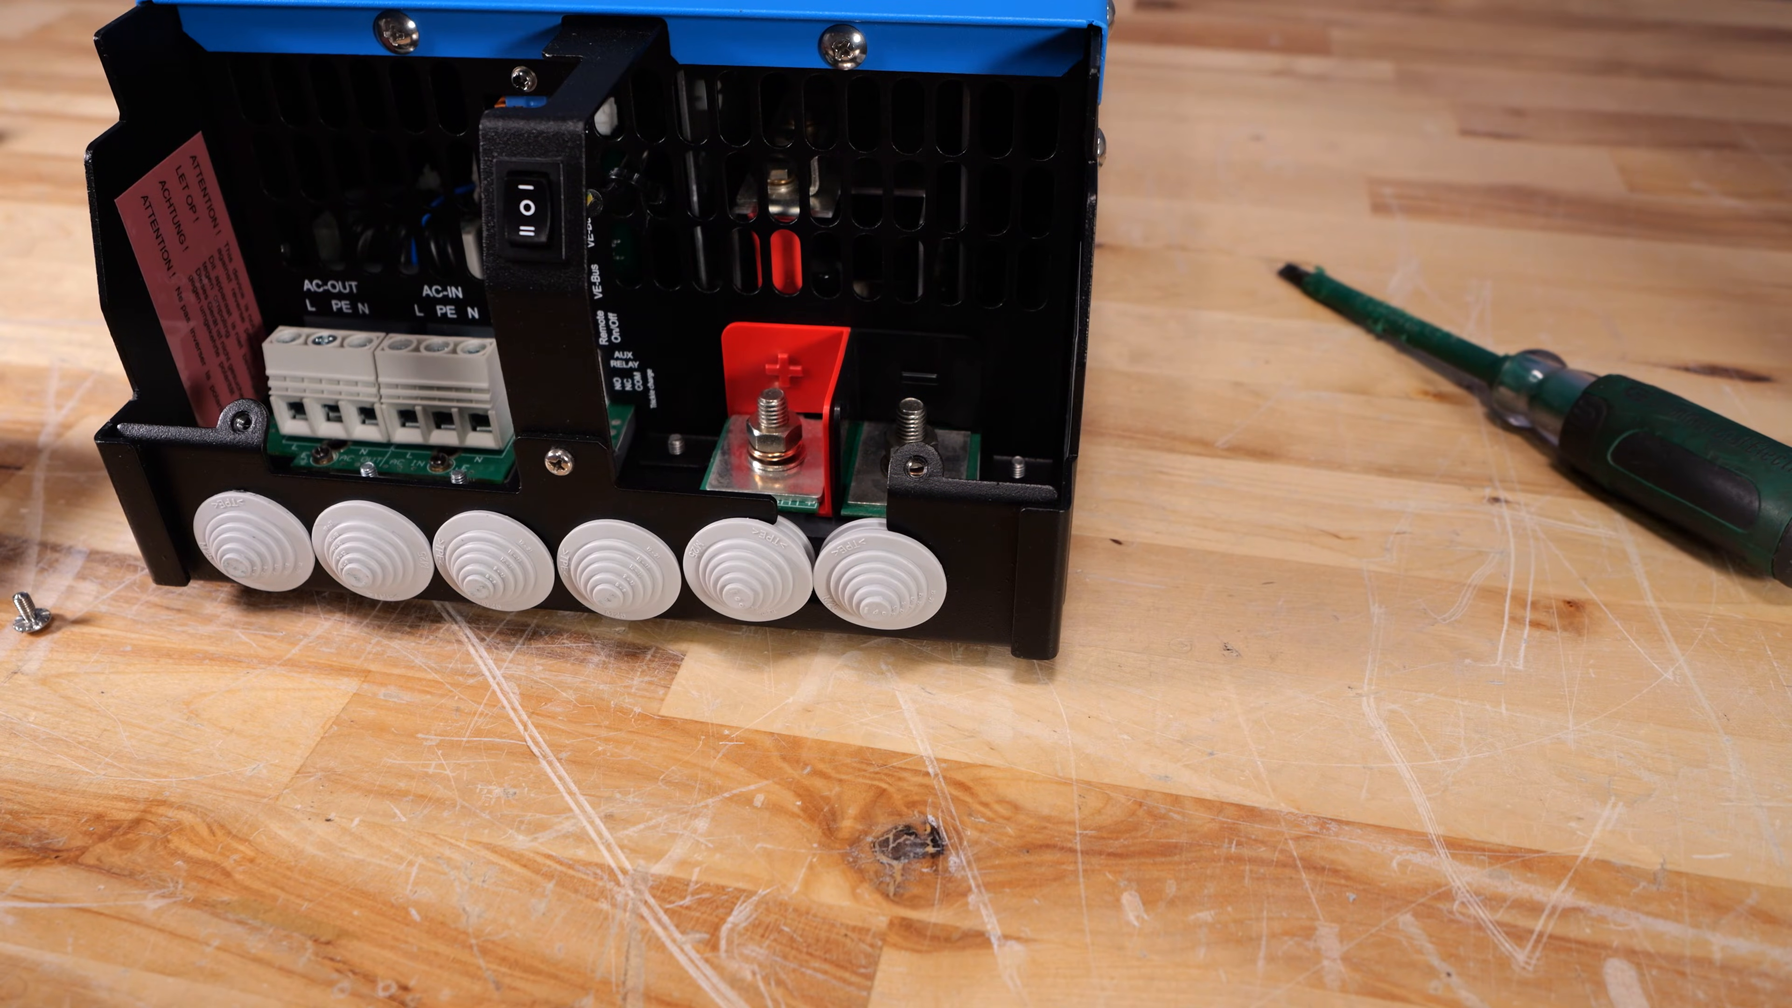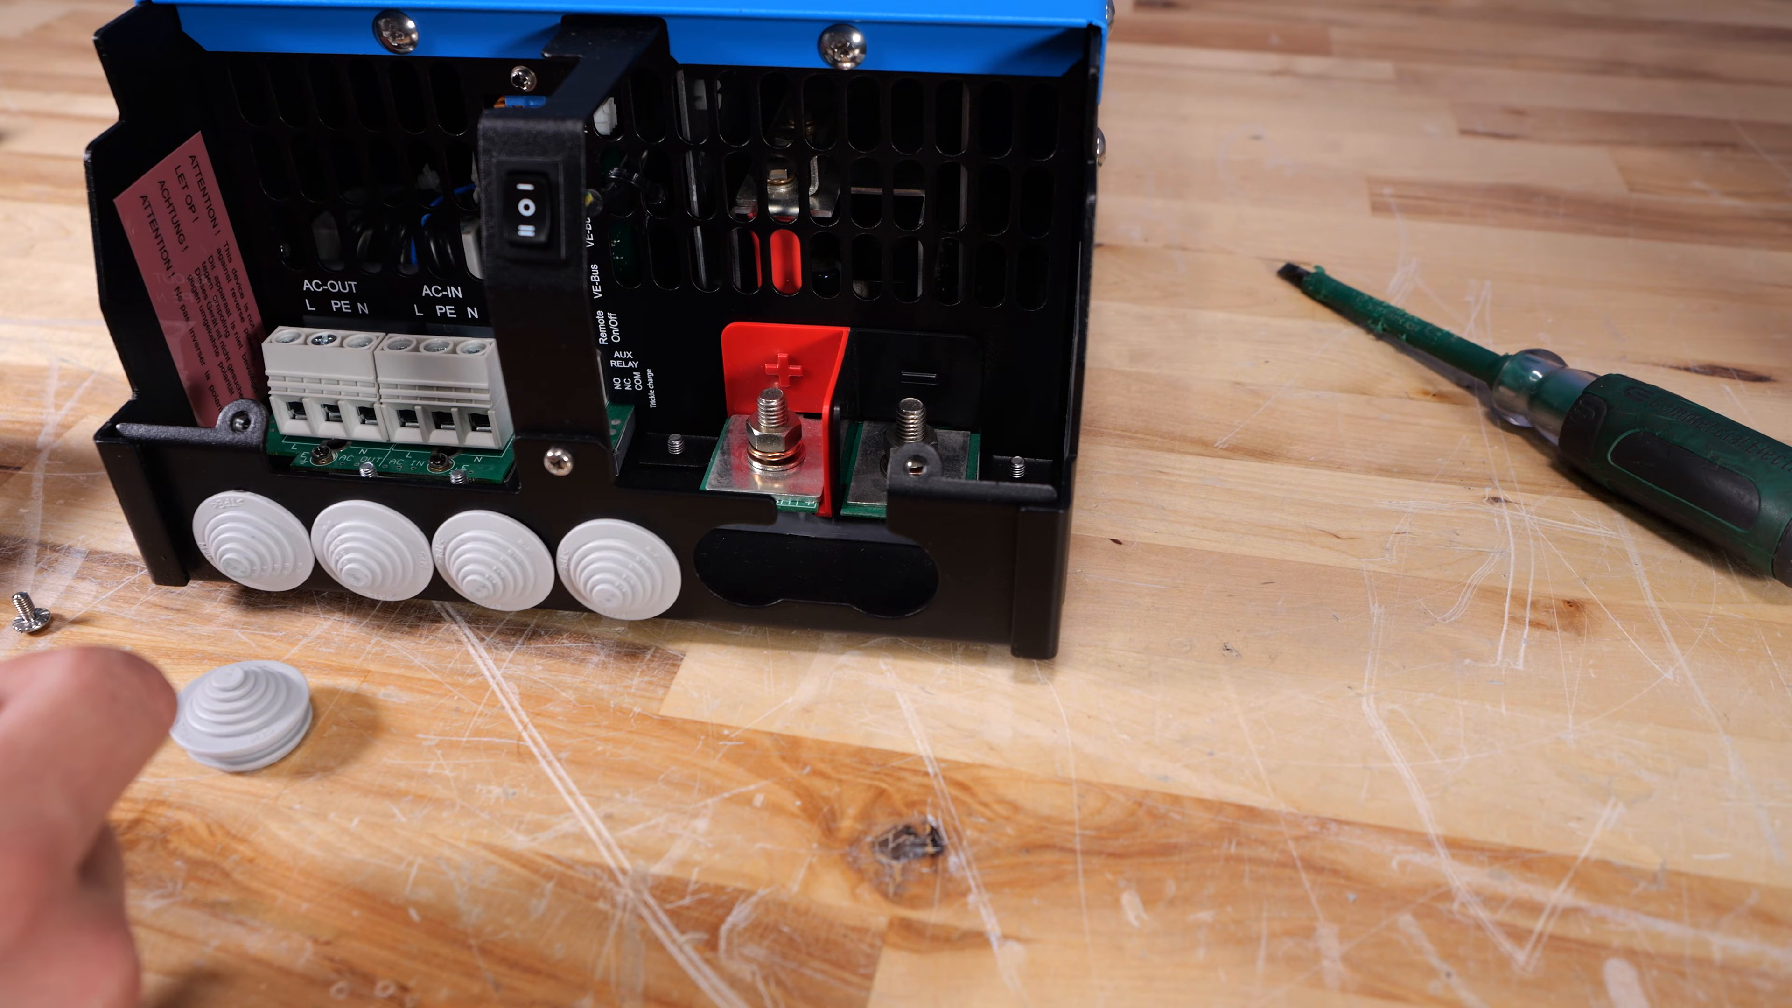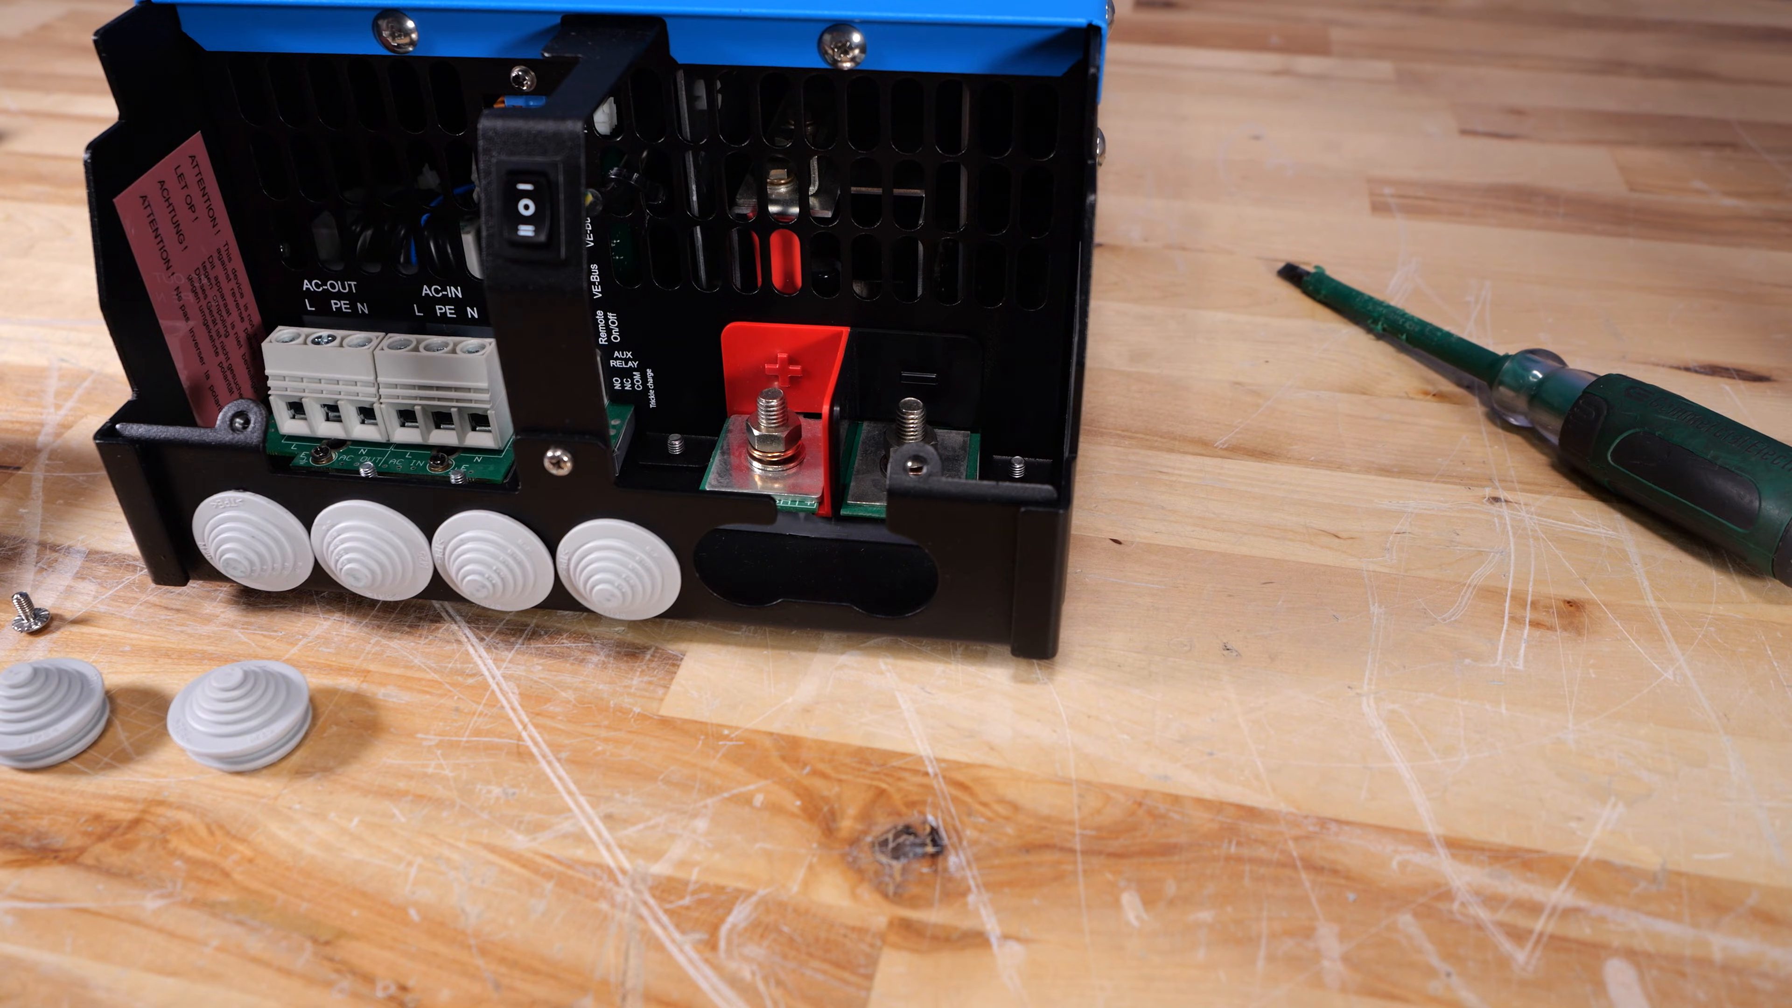As far as getting your cabling in and out of the inverter, they have these dust-proof glands I mentioned, and they made a nice notch in here, so if we remove the terminals for the battery, you can easily get your battery cable in here and get it in without trying to fish it through a really tiny hole. Now for this inverter, we're not pulling that much current. It's about 40 amps at most, so I typically recommend the smallest-gauge battery cable we have, and that'll be a 6-gauge. These are M8 studs, so you'll want to use 5-16 ring terminals.